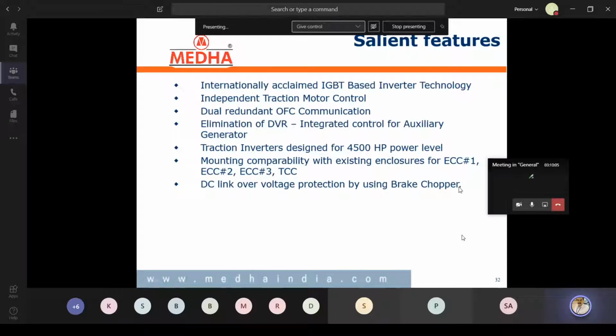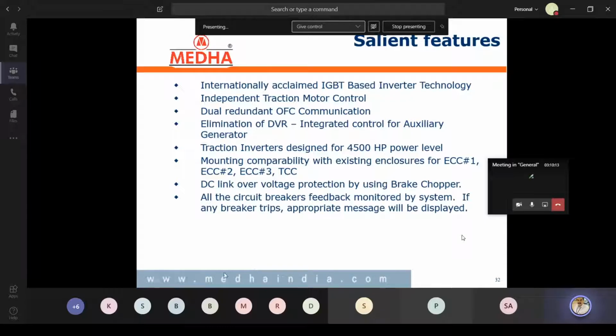DC-link over voltage protection by using a brake chopper. We have already discussed that a brake chopper circuit is designed for over voltage protection. And the feedback of all the circuit breakers is monitored by the system. If any breaker trips, an appropriate message is given to the operator. Almost all the important breaker feedbacks are monitored, and the appropriate breaker tripping or faulty condition is indicated automatically on the display unit. For example, the radiator fan 1-2 breakers feedback: the system monitors that continuously and gives the appropriate fault message accordingly.